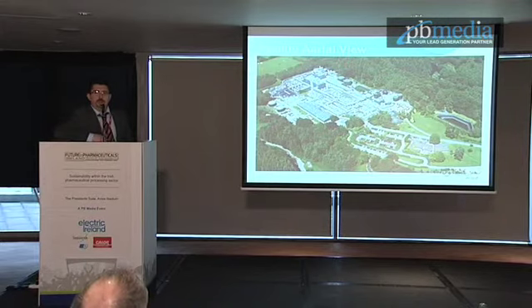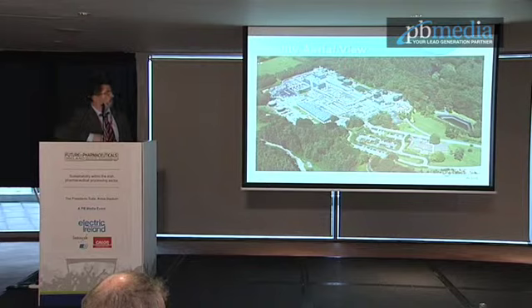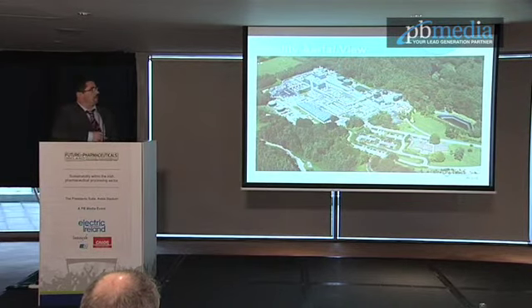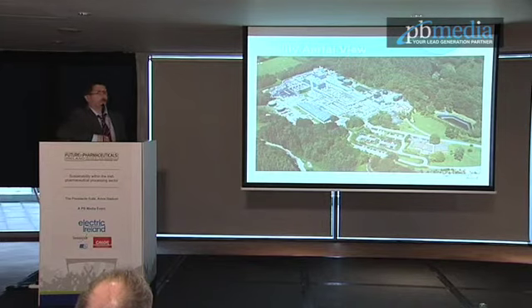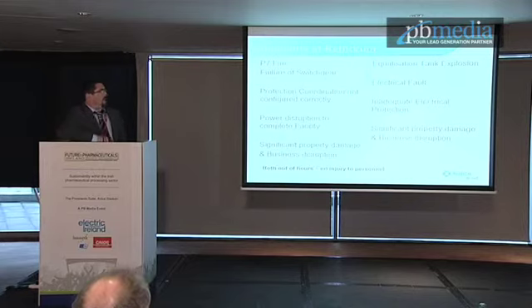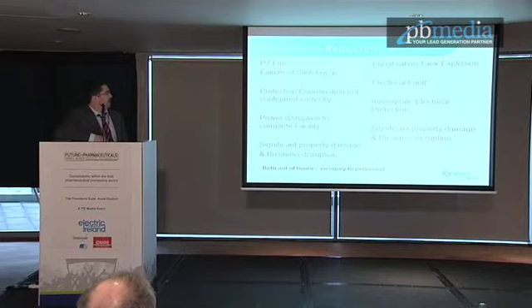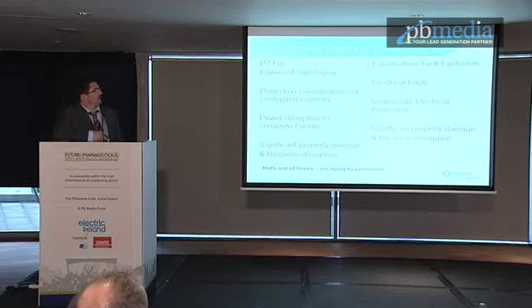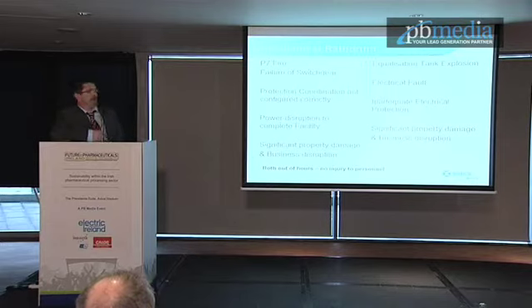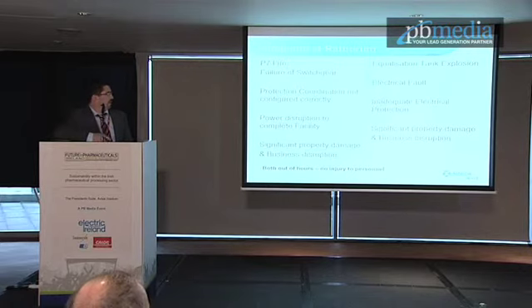As the site grew, there were various pulls on finances and resources, so the electrical infrastructure may not have got the attention or the focus that it needed. As a result, in the last 10-year period, there were two significant incidents in Rathdrum. The first one was a fire in our P7 facility, which resulted in a failure of switchgear caused by inadequate protection coordination, which resulted in power disruption to the entire plant and significant property damage. The second incident was an equalization tank explosion. Again, it was an electrical fault. It had inadequate electrical protection and again had significant damage. Luckily, both of these incidents were out of hours, so no one was actually injured in either of them.